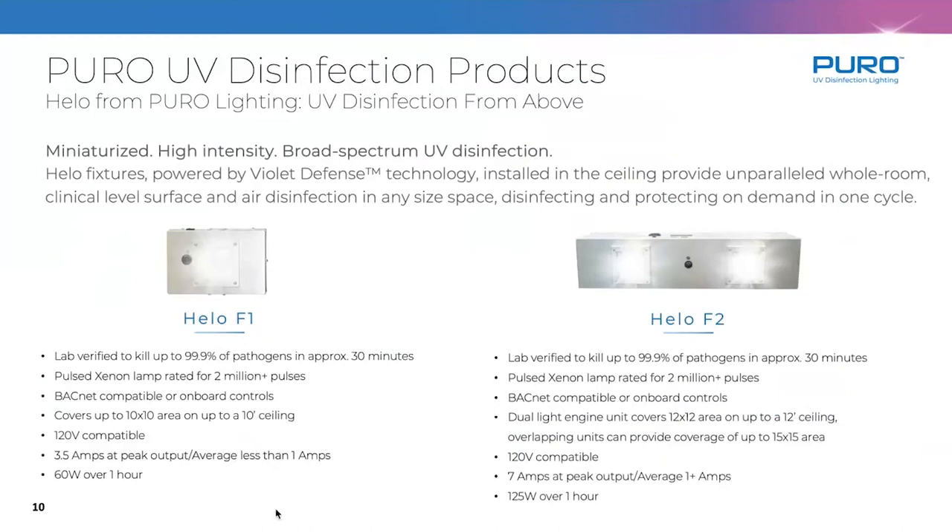Installing the units gives you automation of disinfection. We can connect to the building automation system, use wireless control systems like nLight AIR to schedule and control it, and we have BACnet compatibility built right in. Very low power consumption — on average less than an amp on the F1 and just over an amp on the F2. Think two to three dollars worth of energy per year at nine cents per KWH.